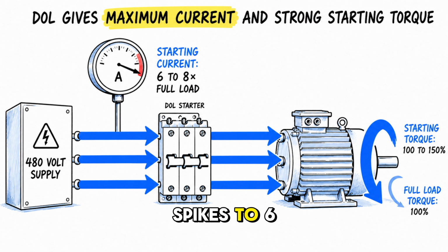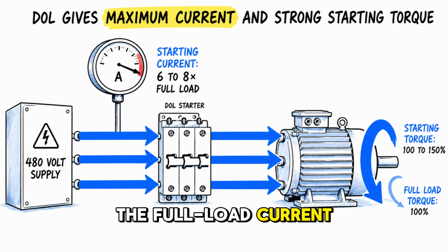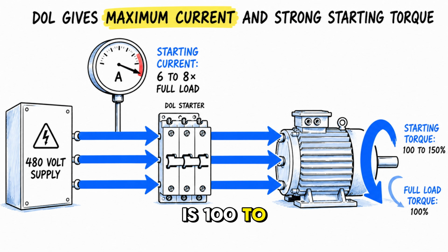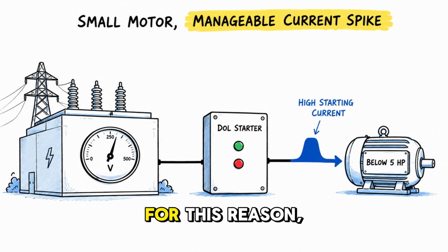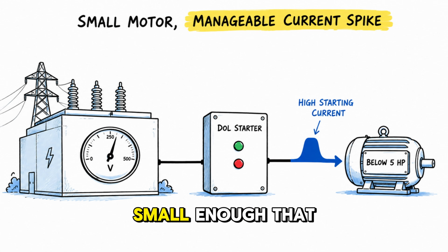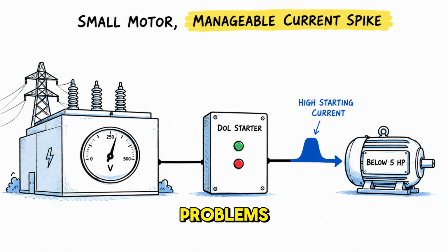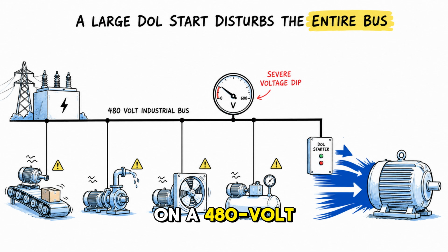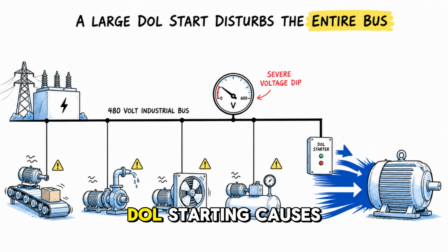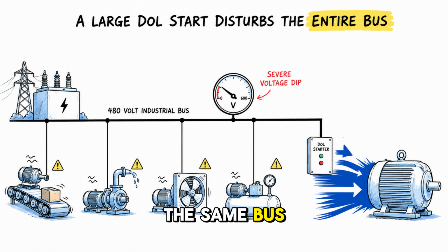The starting current spikes to 6 to 8 times the full load current. The starting torque is 100 to 150% of full load torque. DOL gives maximum starting torque, but it also causes the maximum current surge. For this reason, DOL starting is only used for small motors below 5 horsepower. At that size, the starting current spike is small enough that the supply network can absorb it without problems. For large motors on a 480-volt industrial supply, DOL starting causes severe voltage dips that affect every other machine on the same bus. This is completely unacceptable in a factory environment.